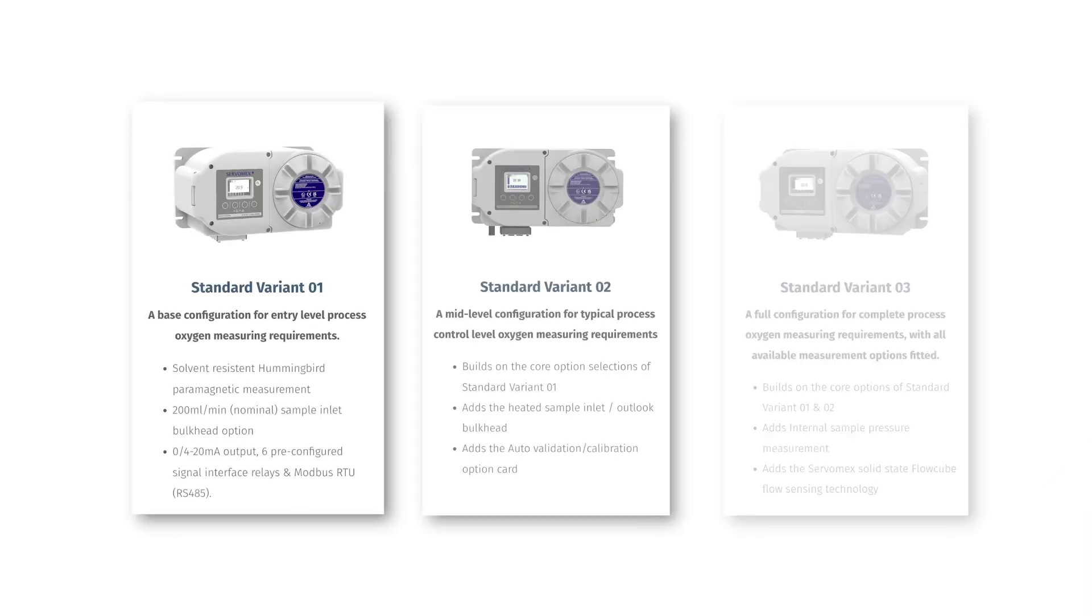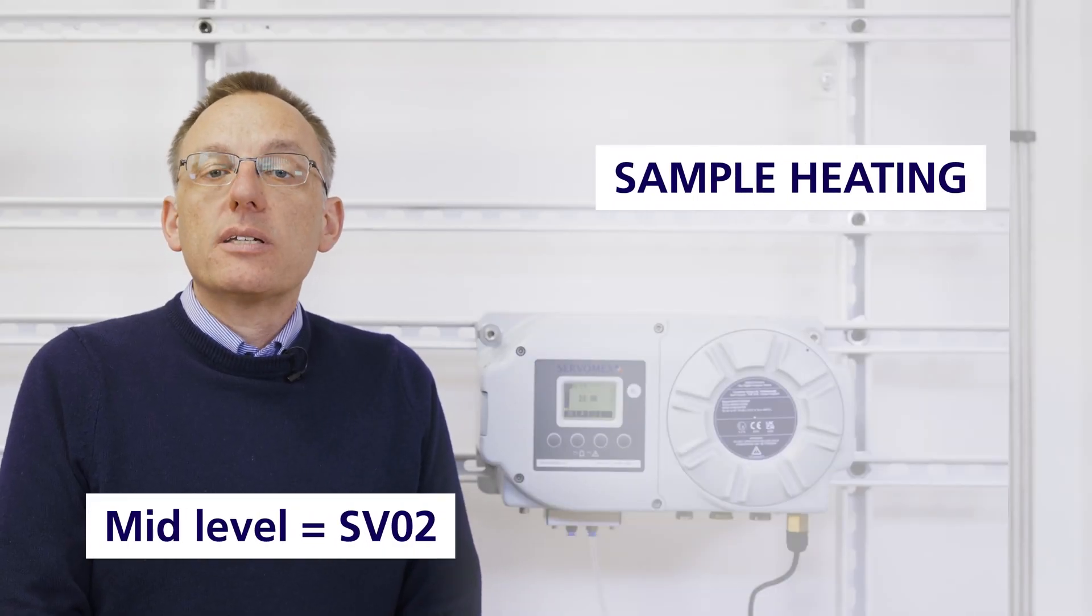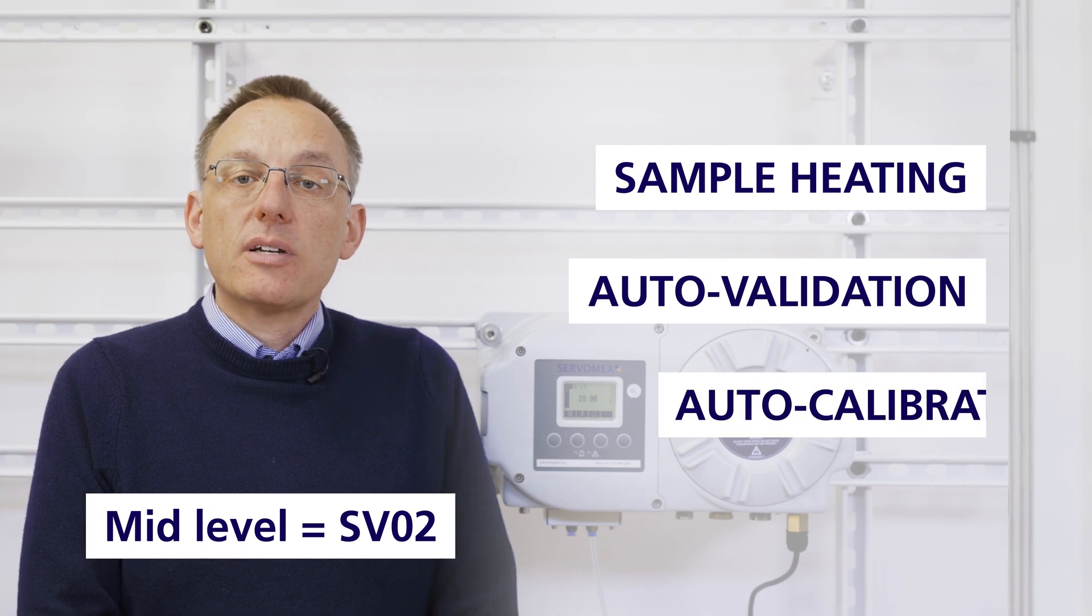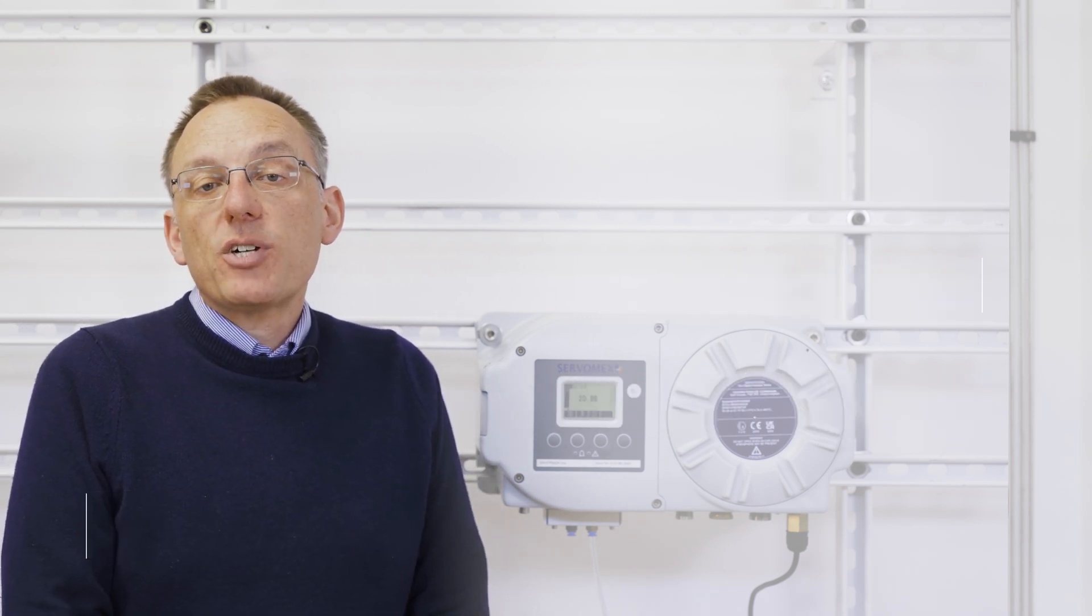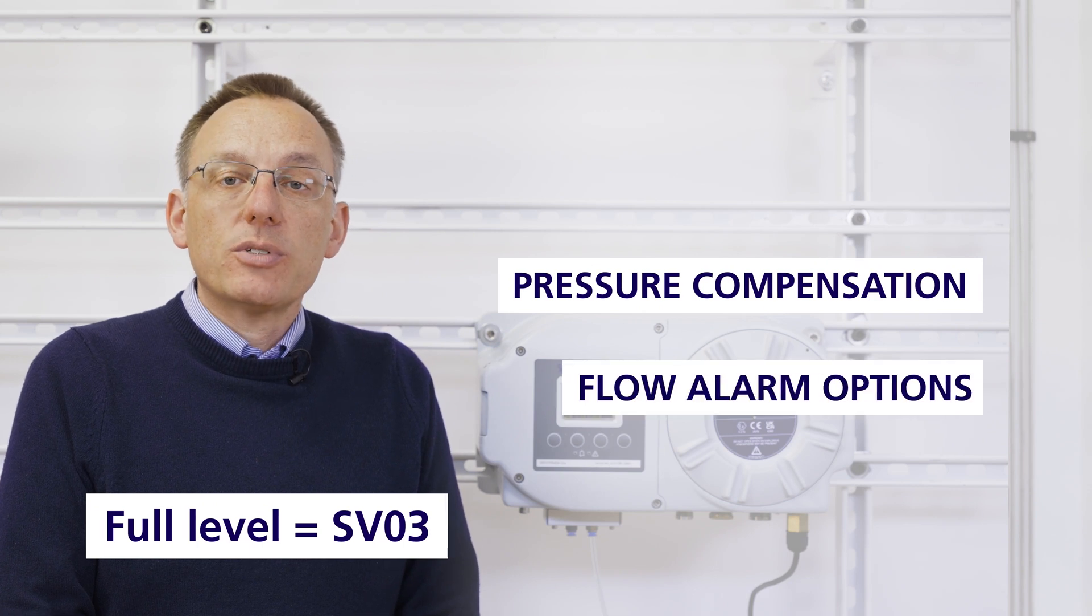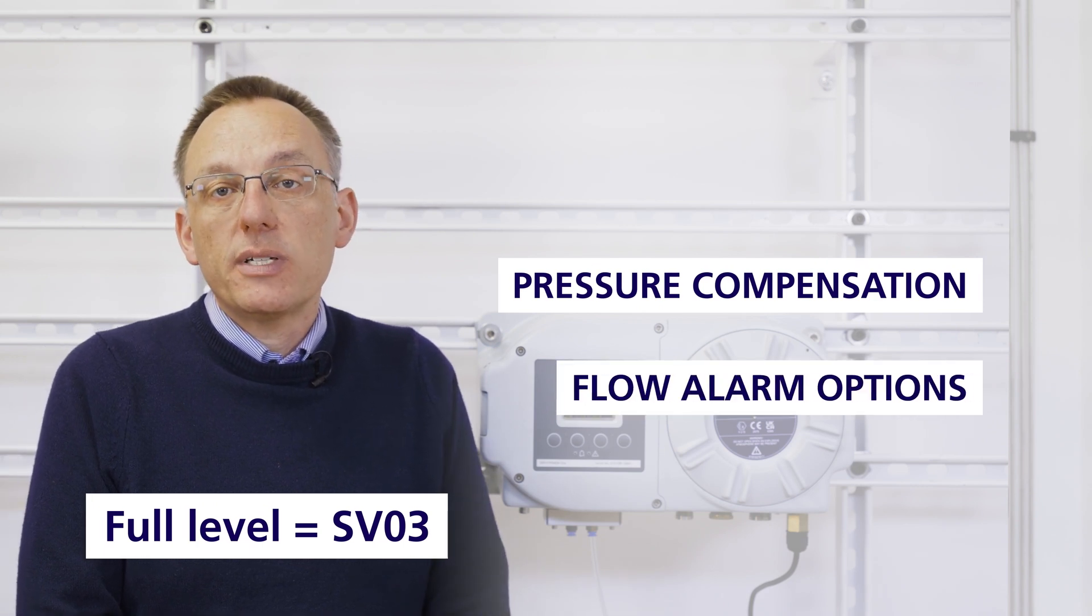Three pre-configured standard build variants are available for quick turnaround covering the most commonly chosen options. The base level variant includes the solvent-resistant transducer for general oxygen measurement requirements. The mid-level variant adds sample heating, auto-validation and auto-calibration. And the full variant adds pressure compensation and flow alarm options covering all your process measurement needs.